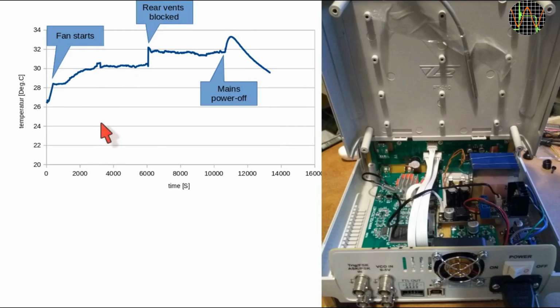and kept everything running for another 1.5 hours before turning the power off, but keeping the recording of the temperature on for a while longer. It is clear that blocking the vents is not a good idea because the temperature jumped up by 2 degrees. I suspect that the fan's suction causes air to enter the vents and swirl in a much larger curve than expected through the entire enclosure before exiting back out through the fan.